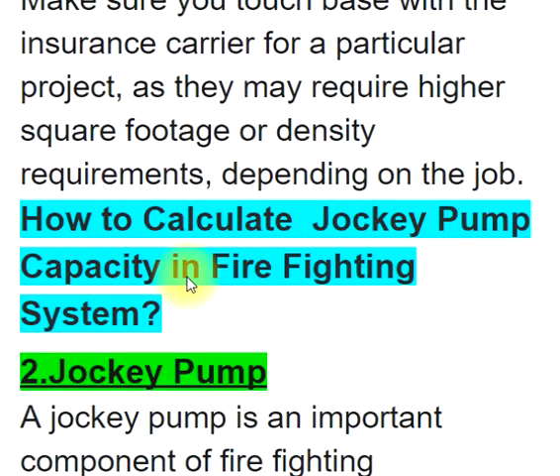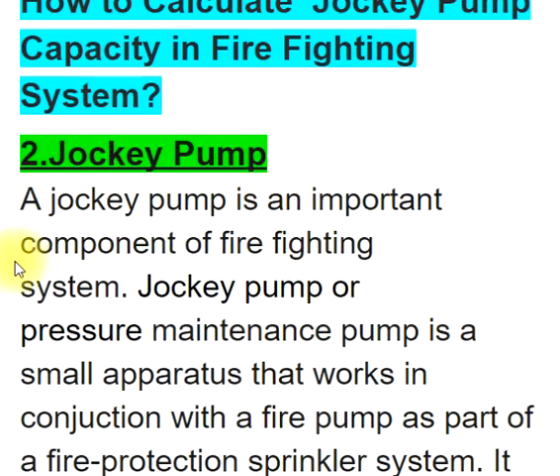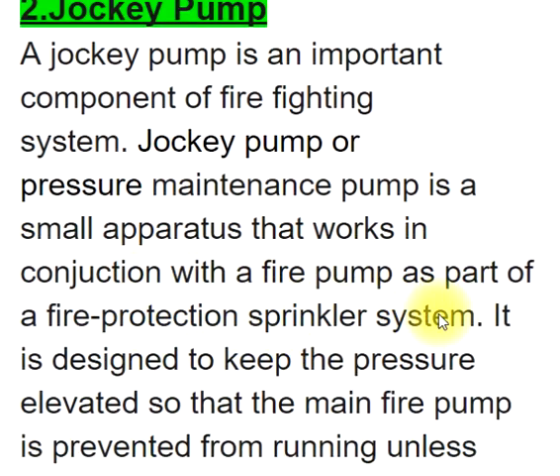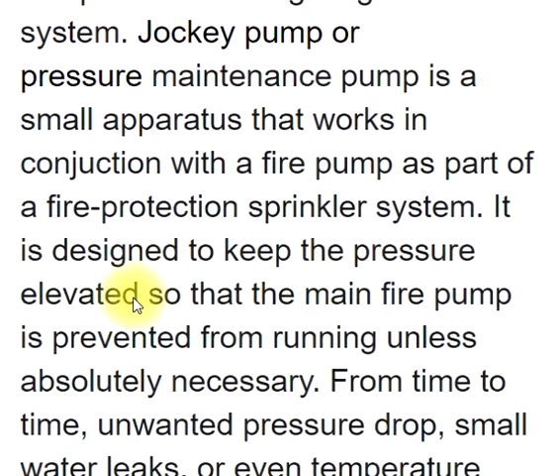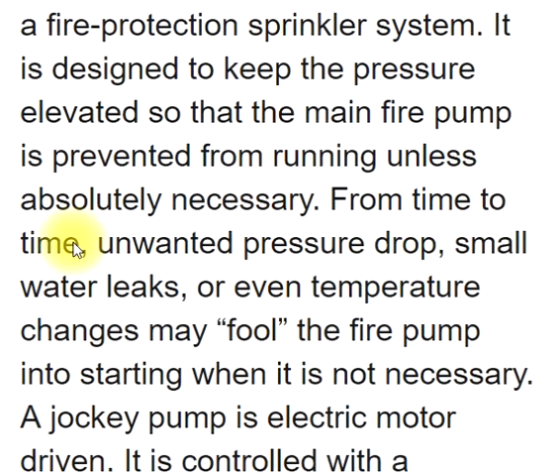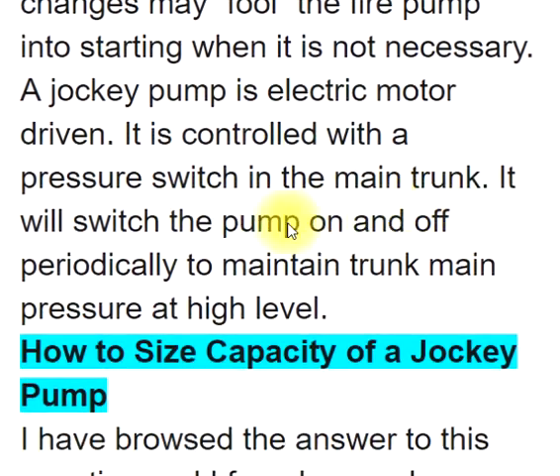Jockey Pump — a jockey pump is an important component of a firefighting system. Also called a pressure maintenance pump, it is a small apparatus that works in conjunction with a fire pump as part of a fire protection sprinkler system. It is designed to keep the pressure elevated so that the main fire pump is prevented from running unless absolutely necessary. From time to time, unwanted pressure drops, small water leaks, or temperature changes may cause the fire pump to start unnecessarily. A jockey pump is electric motor driven and controlled by a pressure switch in the main trunk; it switches on and off periodically to maintain trunk main pressure at a high level.